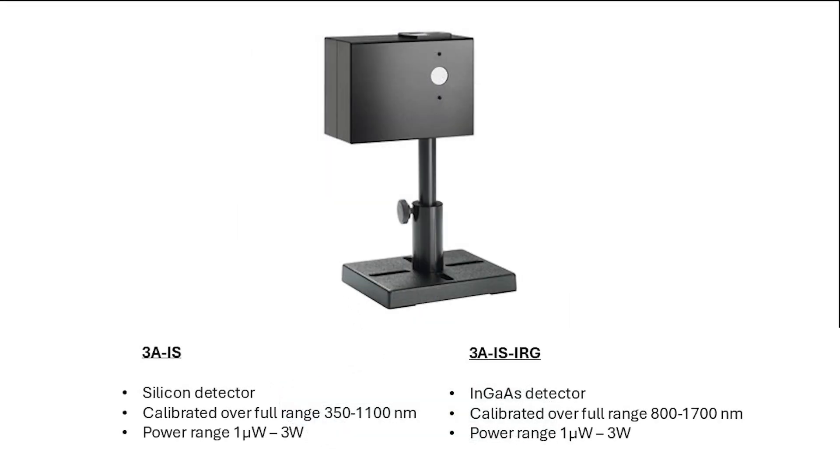Both models of the 3AIS can measure average powers from 1 microwatt up to 3 watts, covering the spectral ranges 350 to 1100 nm for the 3AIS and 800 to 1700 nm for the 3AIS-IRG.